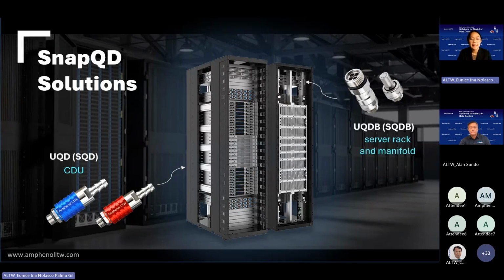The only difference between the two is that SnapQDB is a blind mating solution, while the other is just a normal mating connector. For the UQD, it's mainly used from the control unit for the coolant distribution unit, while the UQDB is for server rack to server rack interconnect. It really requires blind mating because you cannot see the back of the server rack. Once you install this product, there's no way to do a visual check, so you just rely on the mechanical feature of this product. These two are designed for different applications: the UQD is for external connection, and the UQDB is for internal connection between servers.